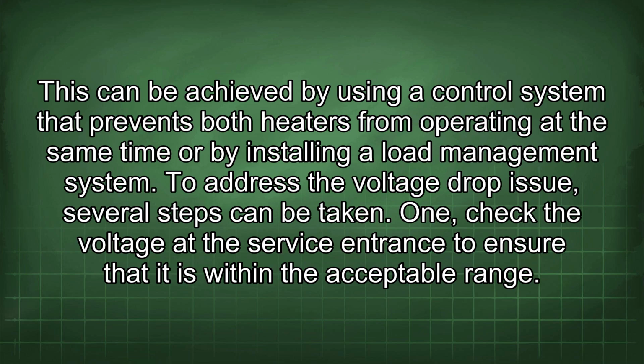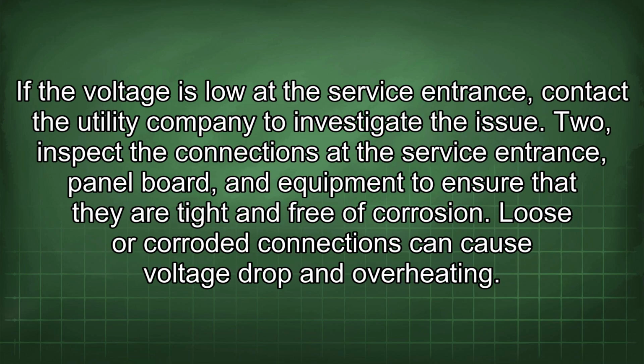1. Check the voltage at the service entrance to ensure that it is within the acceptable range. If the voltage is low at the service entrance, contact the utility company to investigate the issue. 2. Inspect the connections at the service entrance, panel board, and equipment to ensure that they are tight and free of corrosion. Loose or corroded connections can cause voltage drop and overheating.